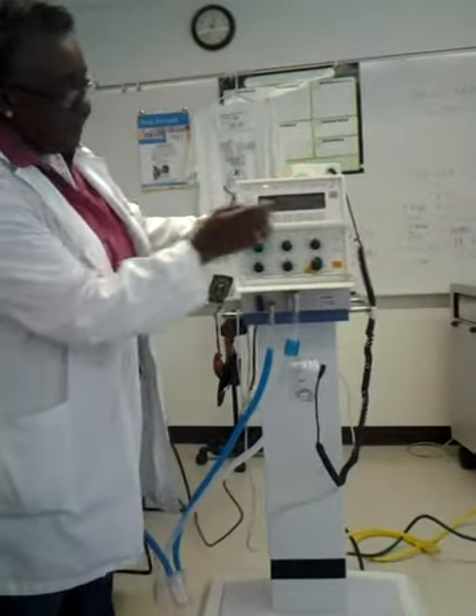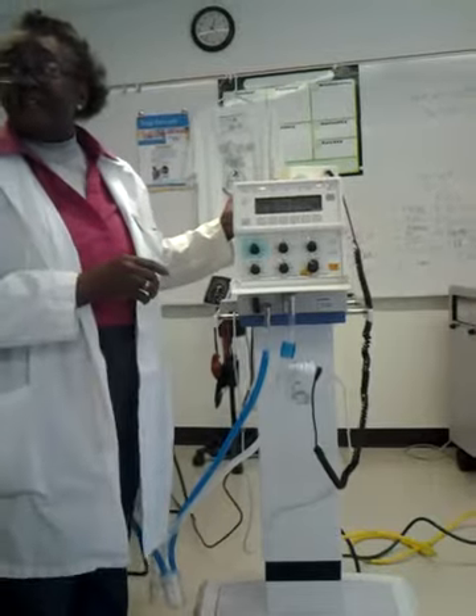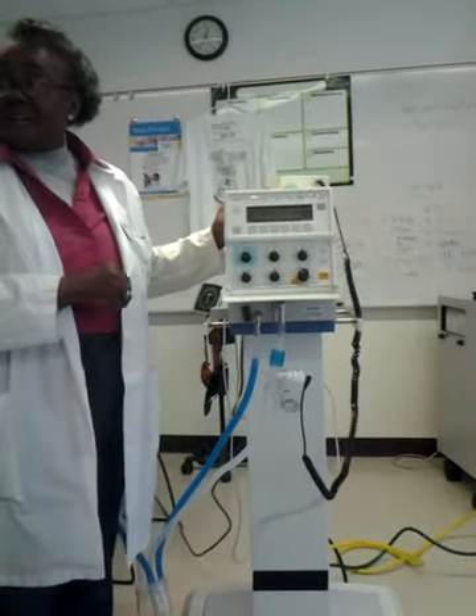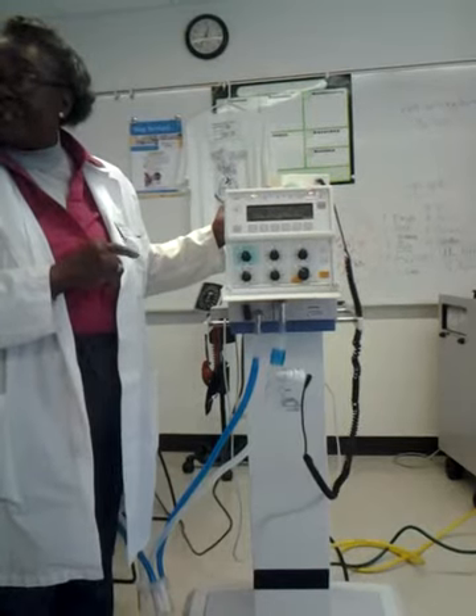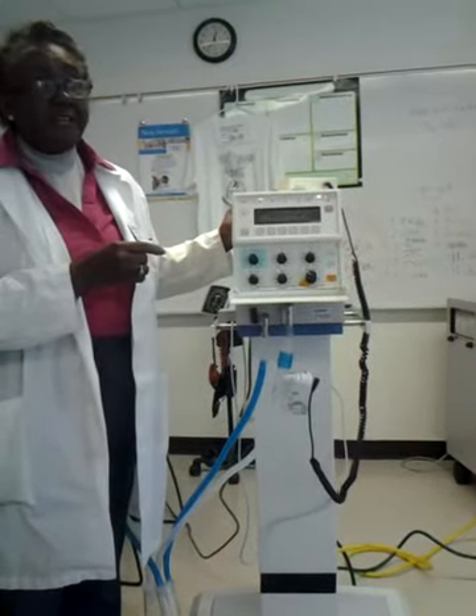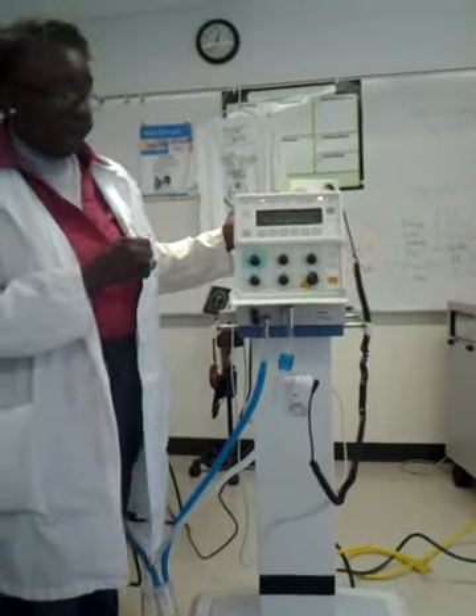So the basic thing that you're going to set up is you're going to make sure that you don't have to do an SST, but as I showed you, you have to calibrate your O2 and you have to calibrate the flow. If I take the flow sensor out of line, then there are some parameters that you can't use, like setting your sensitivity or setting your volume guarantee. So you have to have your flow sensor in line with this particular machine, because it helps you to set your sensitivity and it helps you with that volume guarantee.